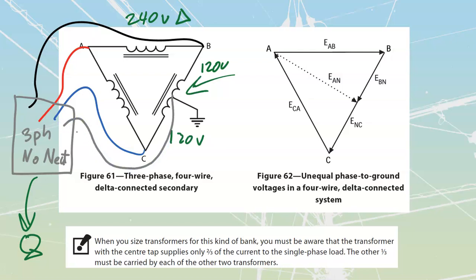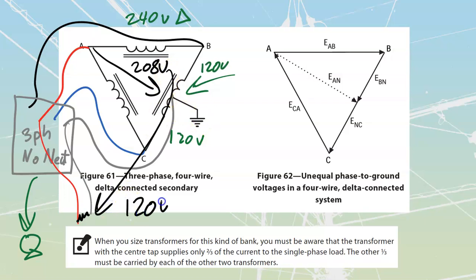there is a danger that somebody might run out a line from my phase A and a neutral, or what they think is a neutral, and put a load across it thinking that they're going to get 120 volts. They're not. What they're actually going to measure across here is 208 volts. And if you place 208 volts over top of a 120 volt load, you are going to have fire, explosions, things like that. Bad times are going to ensue, so we just want to stay away from that type of thing.